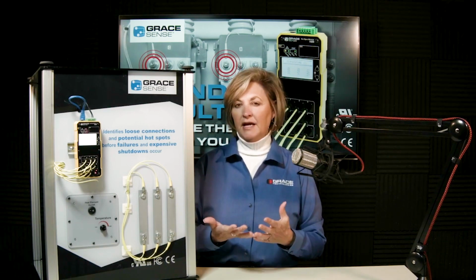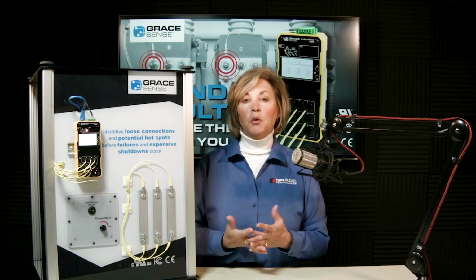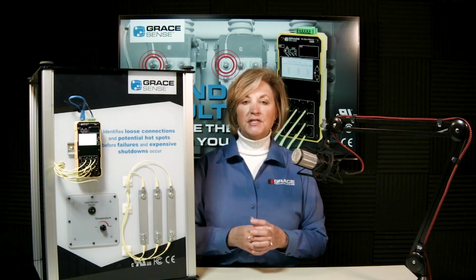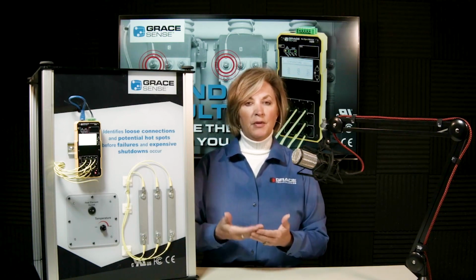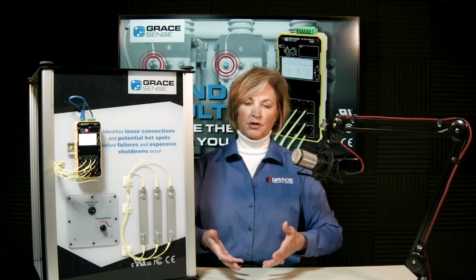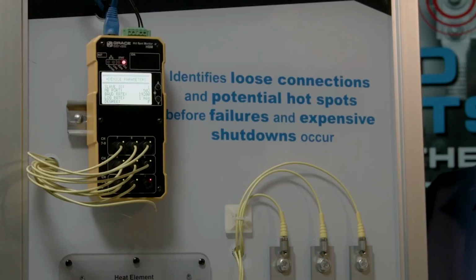We also have another accessory called the Modbus current sensor, and what that does is it behaves like a split core CT, but it attaches to the secondary of a primary CT, and you would do your full scale amp notification inside the web page of the unit itself. But what it does is it allows for the correlation between current and temperature. So the Modbus current sensor would be calculating current, and the temperature would be measuring temperature, and those two values would actually be logged inside the unit itself together. So when you download the data and extract it and put it down on your laptop, you could easily see a trend on what the current is doing in relationship to the temperature.